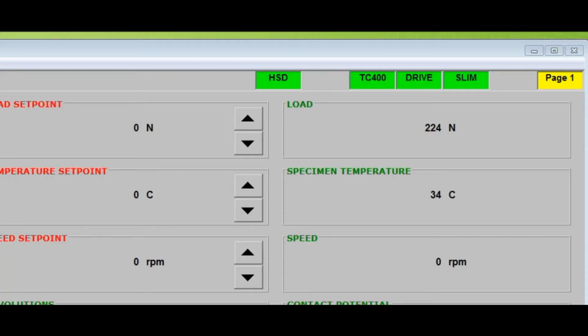There are a number of green boxes on the status bar. These indicate peripheral systems under the supervisory control of the Compen software. For a T91 machine, there are 4 peripheral components. The slim box refers to the Serial Link Interface module, which provides a microcontroller-based distributed control and data acquisition interface between the front-end software and the machine. A green box indicates that two-way communications has been established between the PC and the interface.